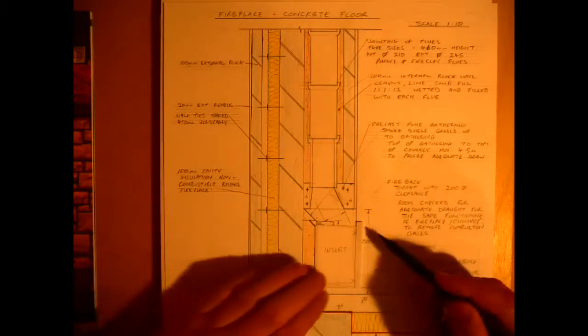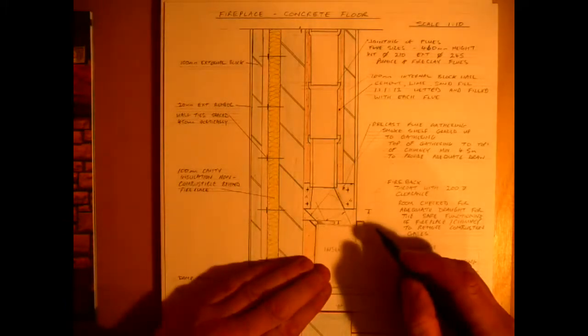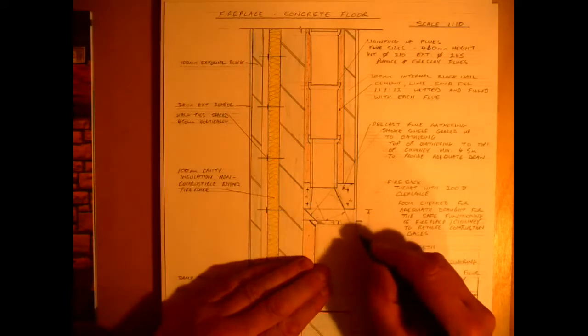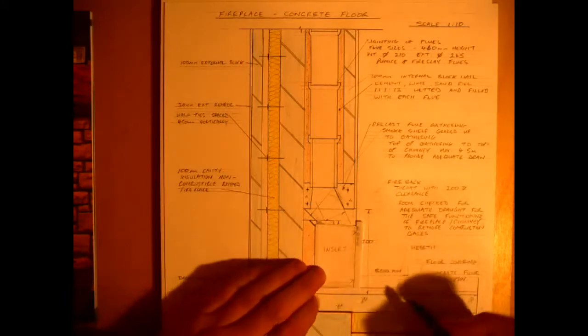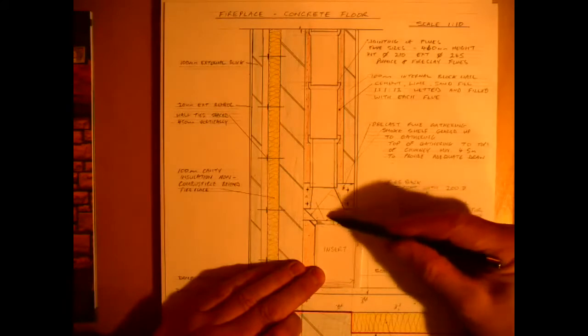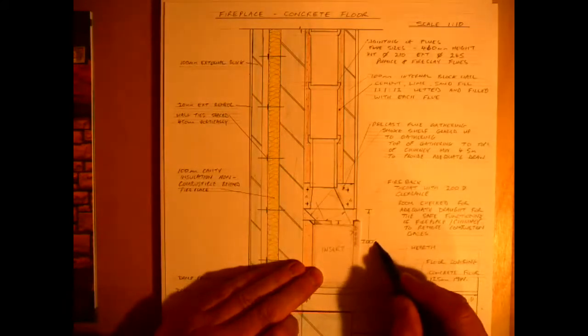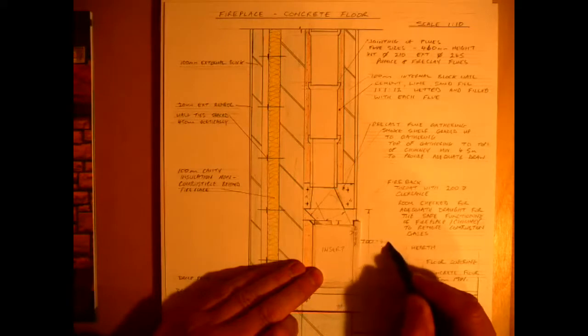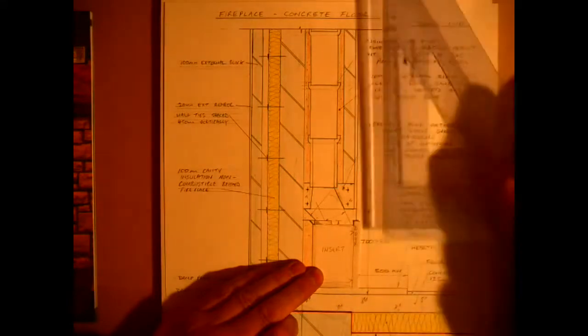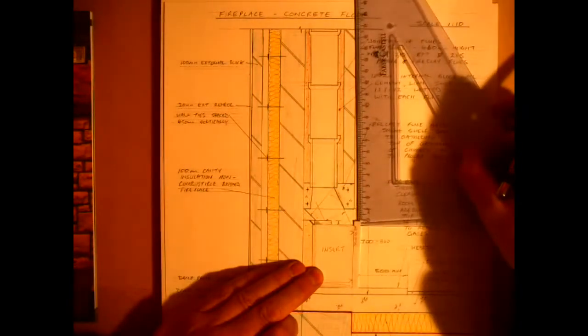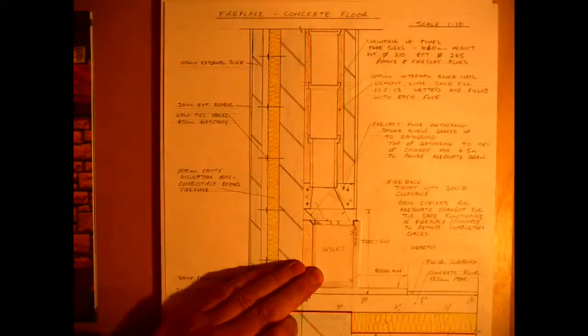I don't have an awful lot of space above this here, so the flue gathering could be increased maybe in height from 700 to 800 or even 900 to allow for a bit more access, and a panel would cover that over at the end of the day, and it would also allow you a bit more room to get in to connect the flue. So you can see there that I've only got 100mm. That's not really a lot of space to get in to the top of that there, so that would want to be increased to allow for easier access.